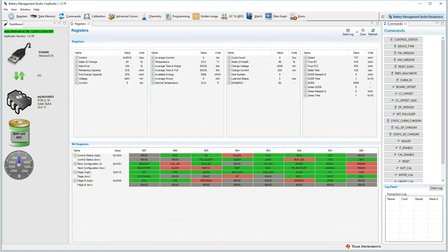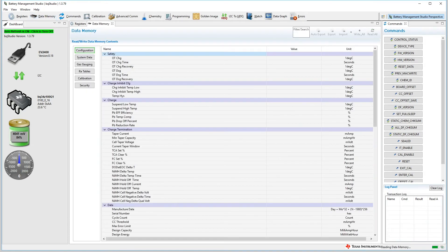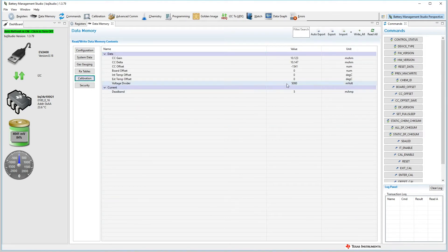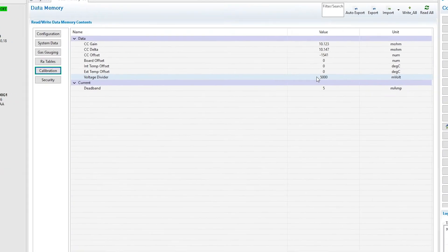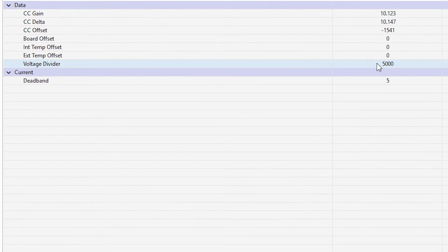With the BQ34Z100G1 dashboard loaded, move your cursor to the ribbon and select data memory to open the data memory window. In the data memory window, select calibration to view calibration parameters. Our parameter of interest is voltage divider, which is set at 5000mV.